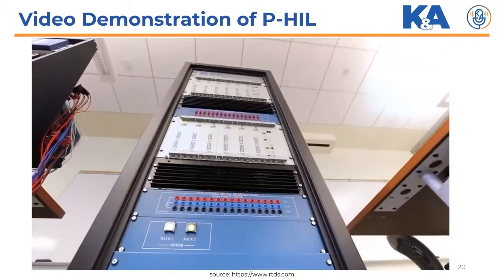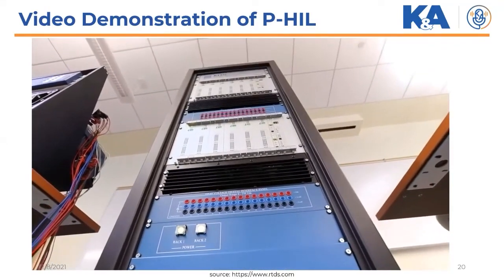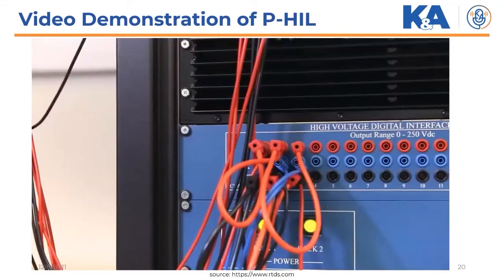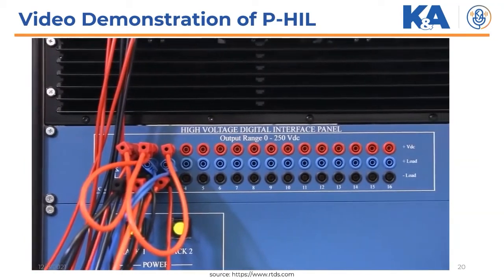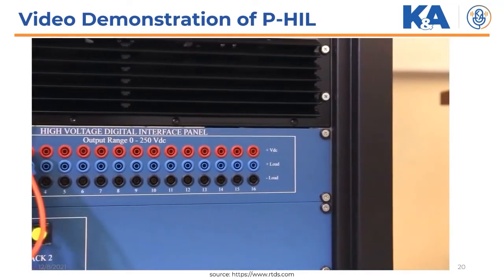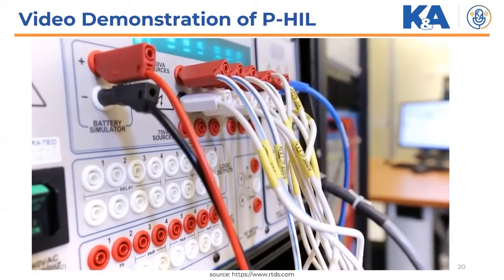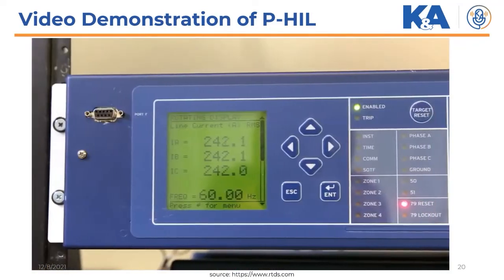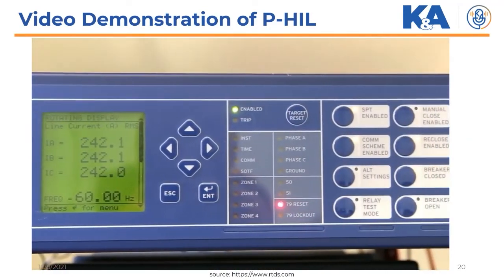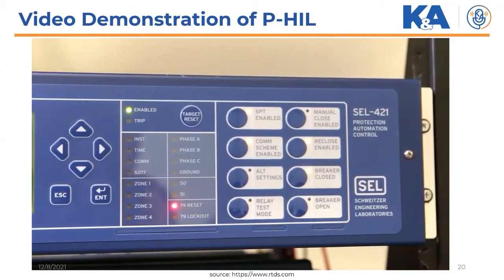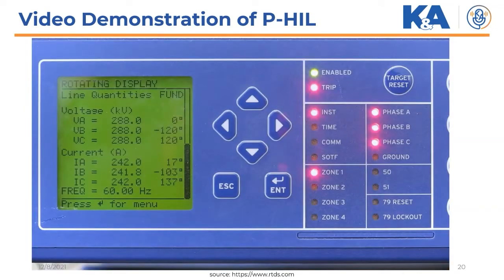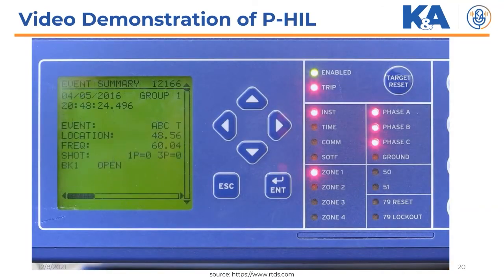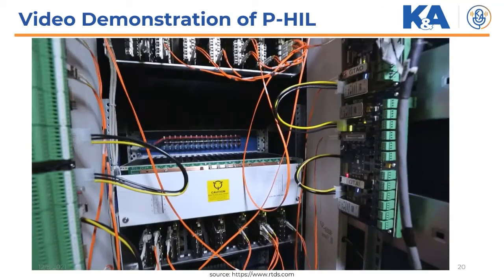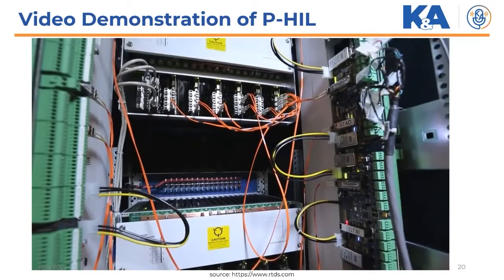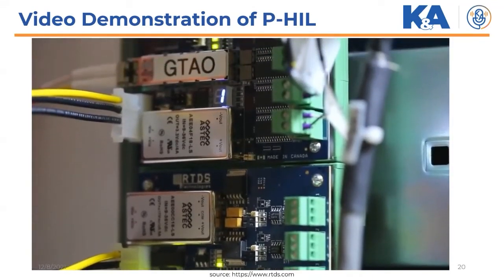The high voltage panel component is used to define signals to be communicated via the high voltage digital output panel mounted in the RTDS simulator cubicle. This panel is capable of switching at station level voltage, and here it's used for breaker status signals. In this demonstration, the user can trigger a fault to check for the correct response from the physical distance protection relay. The voltages and currents will be sent out of the simulation via the RTDS simulator's GTAO card.